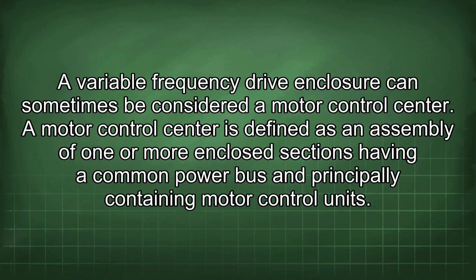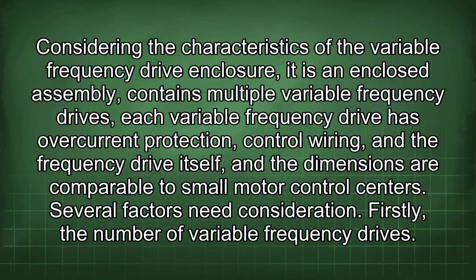A variable frequency drive enclosure can sometimes be considered a motor control center. A motor control center is defined as an assembly of one or more enclosed sections having a common power bus and principally containing motor control units. Considering the characteristics of the variable frequency drive enclosure, it is an enclosed assembly.